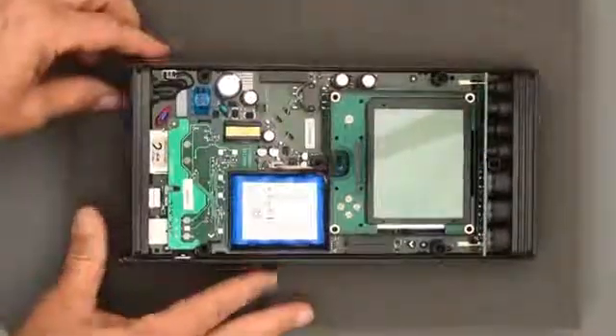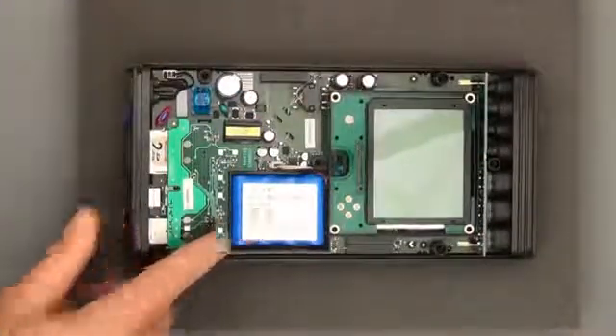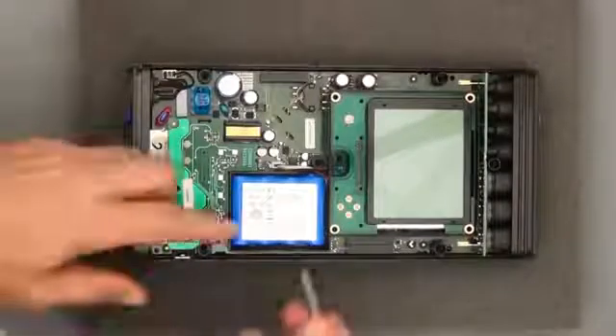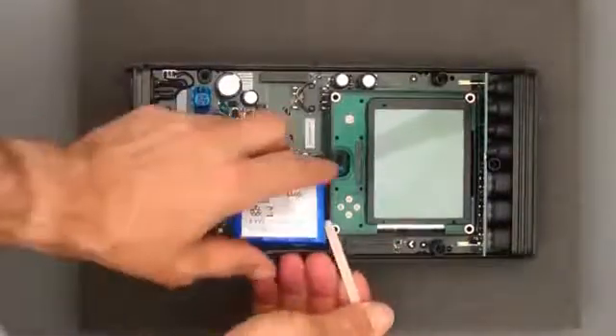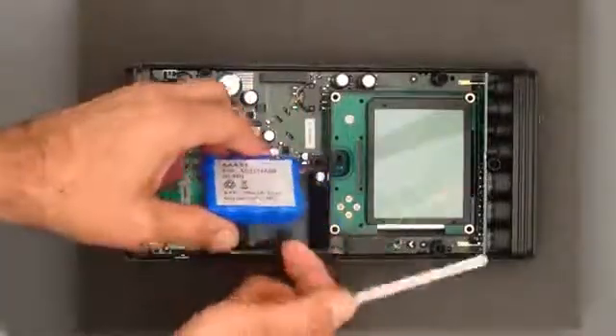With the front cover removed, locate the battery pack inside the PEL. Gently remove and unplug the battery. A small implement such as a drink stirring stick, as shown on the screen, can be useful for doing this.